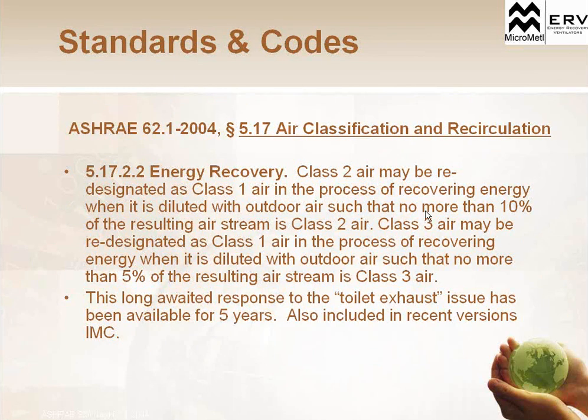The air classification recirculation dictates when an energy recovery unit can bring Class 2 air to Class 1. Class 2 air may be redesignated as Class 1 air in the process of recovering energy when it's diluted with outside air, no more than 10% of the returning air stream. So we can use 10% return air with some unbalanced or fresh air coming in, we can dilute that air so we can actually change the classification.